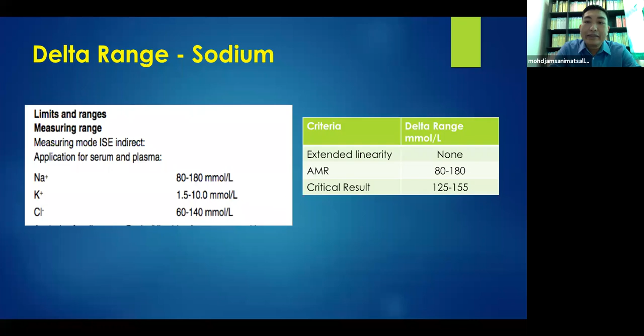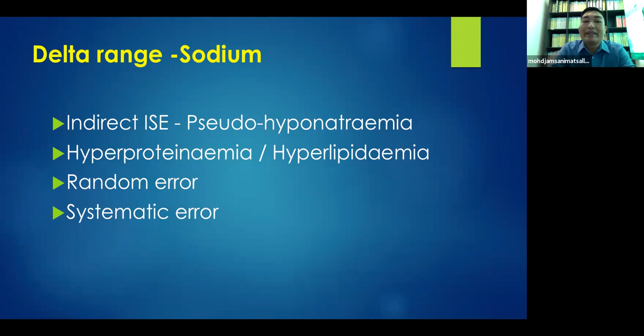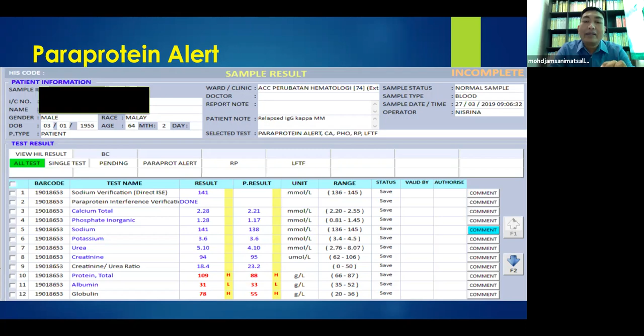The same goes for sodium, the linearity that we choose. We need to decide whether there is a possibility of pseudo-hyponatremia due to hyperproteinemia or hyperlipidemia, and we also need to rule out whether there is evidence of random error or systematic error. So one of the things we created is our paraprotein alert: if total protein is high, we will add on sodium verification with direct ISE, using our ABG analyzer, to make sure the result is verified and there is no evidence of pseudo-hyponatremia in the system.